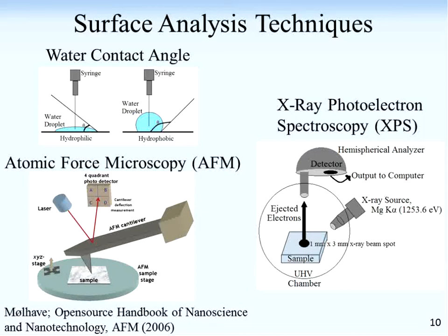Finally, there's X-ray photoelectron spectroscopy, or XPS. This is a quantitative elemental analysis technique — it tells you what elements are present in your surface and in what concentrations. You irradiate a surface with X-rays that knock electrons out of the surface; the electrons come out with a distinct kinetic energy equal to the energy of the X-ray minus the binding energy for the orbital the electron came from. It's sensitive only to the top few nanometers of a surface — about five to ten nanometers — so it's a true surface analysis technique.